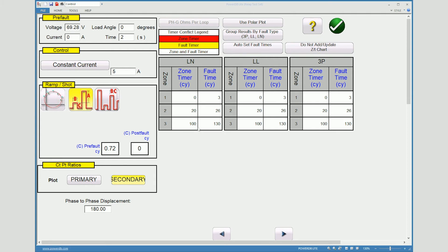You also see that the zone three setting is 100 cycles and we are pulsing that fault for a little bit over the 100 cycles to 130. And we do the same for line to line and for the three phase fault as well. Now I'm going to hit OK.